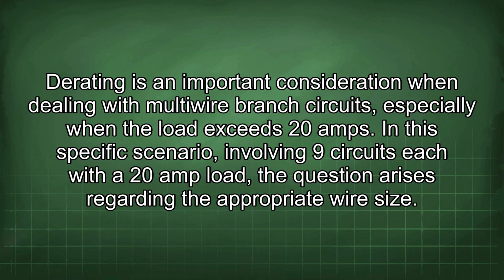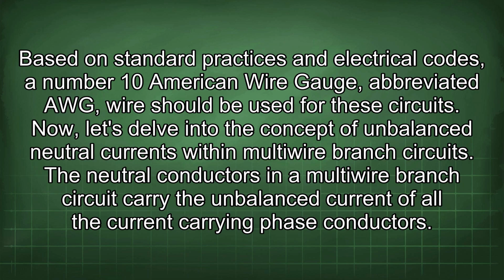Derating is an important consideration when dealing with multi-wire branch circuits, especially when the load exceeds 20 amps. In this specific scenario, involving 9 circuits each with a 20 amp load, the question arises regarding the appropriate wire size. Based on standard practices and electrical codes, a number 10 American wire gauge, abbreviated AWG, wire should be used for these circuits. Now let's delve into the concept of unbalanced neutral currents within multi-wire branch circuits.